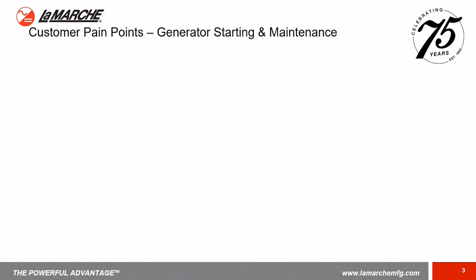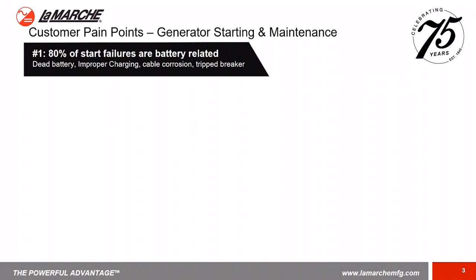Before I begin on the hybrid capacitor module, here are some pain points that customers have faced when starting their generators. The number one reason, 80% of start failures are battery related. A dead battery can cause that. Improper charging, whether it's the wrong charging voltage or the charger itself. Cable corrosion or a tripped breaker that's providing power to the starting system.